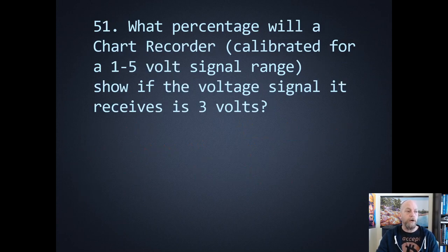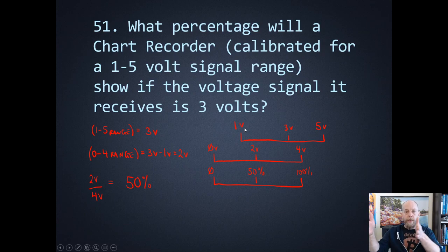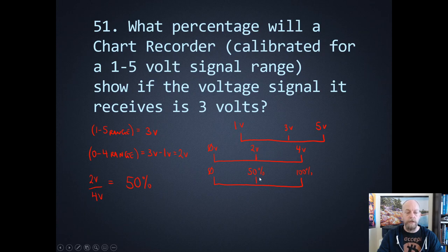Number fifty-one: what percentage of a chart recorder calibrated for a 1 to 5 volt signal range will show if the voltage received is 3 volts? We have an elevated zero on the 1 to 5 volt range. 3 volts on a 1 to 5 volt scale — you can't just take 3 divided by 5. There are 4 equal values between 1 and 5. So 3 volts on a 1 to 5 scale is the same as 2 volts on a 0 to 4 volt scale. 2 divided by 4 gives us 50% of the range.